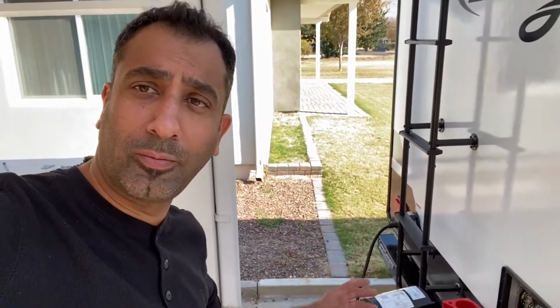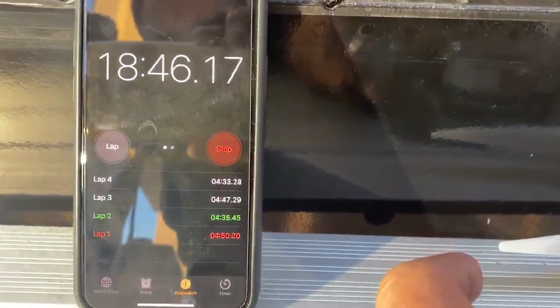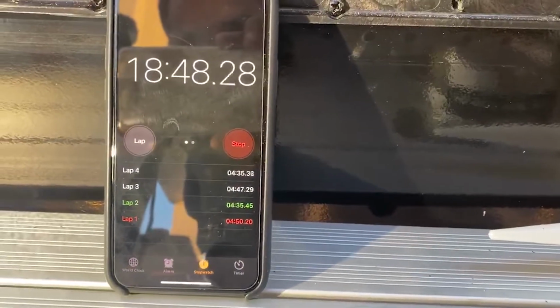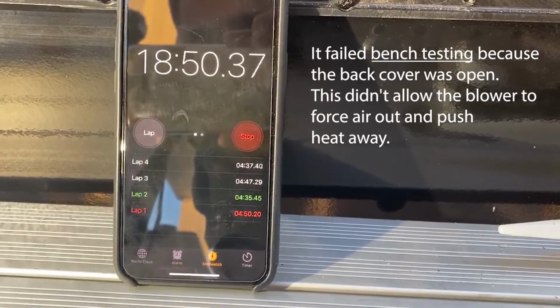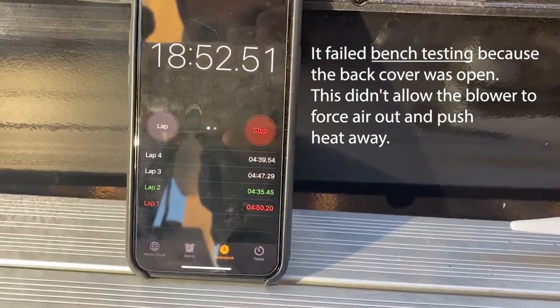I will start with the igniter and see if it's working. If it doesn't, then I'll replace the gas valve. That way I know which part was failing on me. Yes, very frustrating. Nothing really worked, and our furnace kept short cycling every 5 minutes, both inside the unit and outside of it on a bench test.